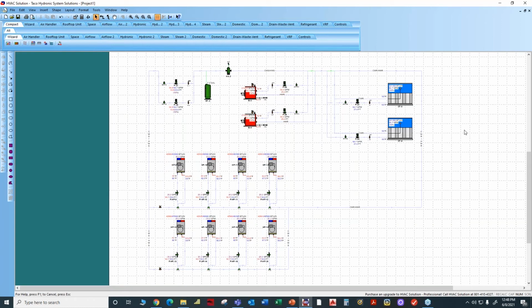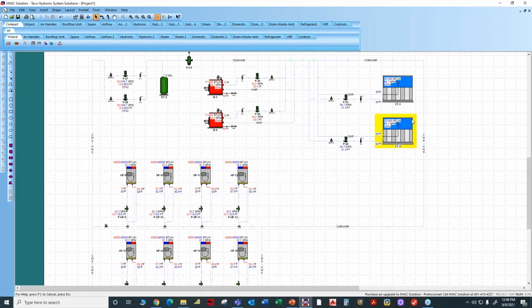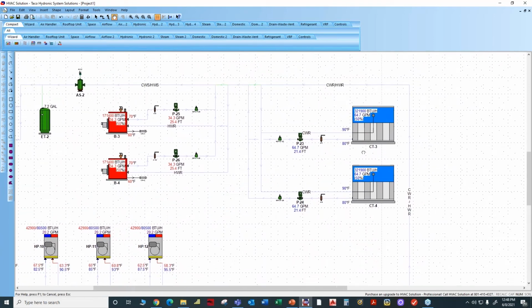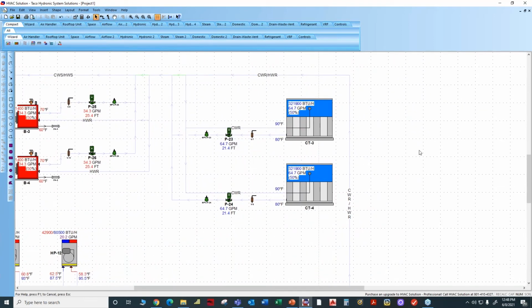So what some of the differences I see when I work with folks is when I look at this type of design right here, we have a cooling tower, pretty traditional, especially for a water source heat pump type of job, where the heat pump is in the zone. So the cooling tower can provide that water temperature that the heat pumps love. And then when it comes to the heating, to inject heating, many systems, I see a boiler like Rich shows.